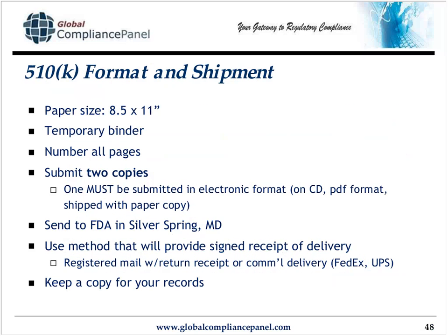When you have your 510K, the hard copy will be standard size. Put it in a temporary binder, usually a loose leaf kind of binder. Number each of the pages. This is probably less of an absolute requirement these days and more of a really good idea, due to the fact that during the review of your 510K, it's going to be much easier for the reviewer to say, well, on page 73, third paragraph, here, please clarify this, as opposed to having to describe what's on the top of that page or the nearest page. Number your pages.